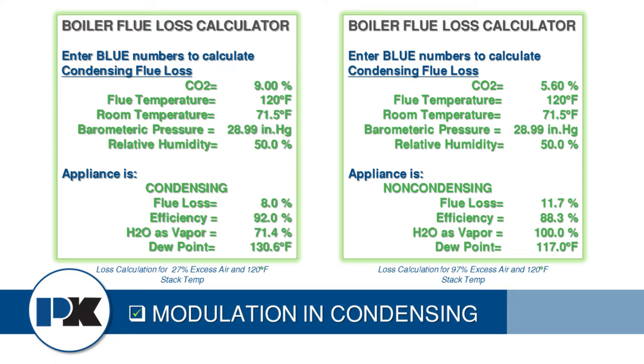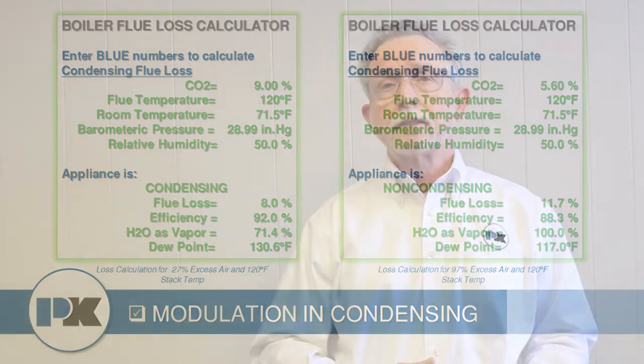Looking at the flue loss calculator: on the left side with 27% excess air for a five to one turndown, the flue temperature is 120 degrees — well below the dew point, so we condense and exceed 90% efficiency. However, that same boiler at 20 to 1 turndown using the excess air method also shows 120 degrees flue temperature, but the dew point has dropped to 117 degrees, so we're not going to condense. This is really the crux of the problem.